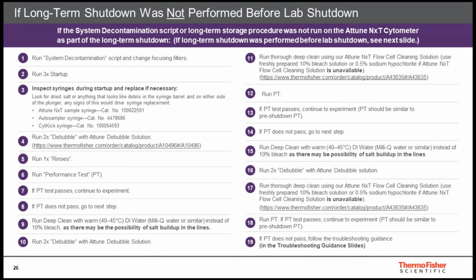experiments. In case the performance does not pass, there is a chance that due to inactivity of the instrument, salt buildup may have occurred in the instrument. The best way to remove it is to dissolve it using warm distilled ultra pure water. Run the deep clean script. However, instead of using 10% bleach, use warm 40 to 45 degrees Celsius DI water. This will help remove salt from the system.